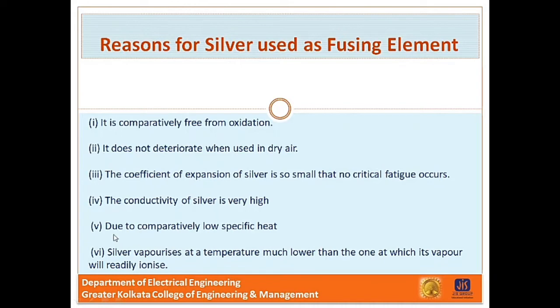Due to comparatively low specific heat, silver fusible elements can be raised from normal temperature to vaporization quicker than other fusible elements. Moreover, the resistance of silver increases abruptly as the melting temperature is reached, making the transition from melting to vaporization almost instantaneous — so operation becomes very fast at higher currents. Lastly, silver vaporizes at a temperature much lower than the one at which its vapor will readily ionize. So when an arc is formed through the vaporized portion, the arc path has high resistance and the short circuit current is quickly interrupted.